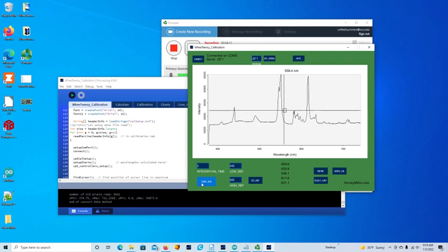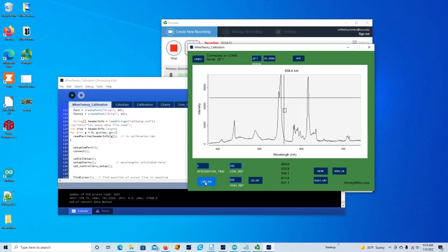Hitting that again, this value is much lower now, but it's not quite what we want. So let's put in another number, let's say 350. We'll hit the set reference, we'll hit the go button, and it accepted that. All right, let's try that again just to make sure that wasn't an anomaly. No, that looks pretty good actually.